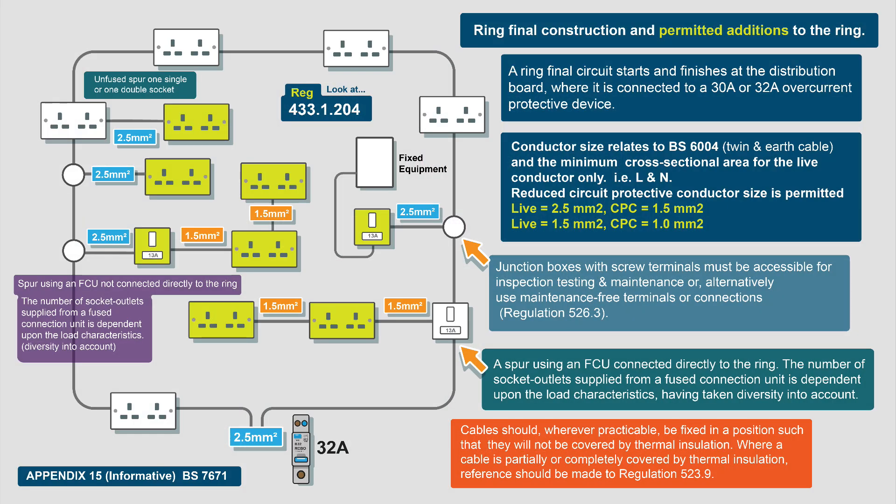In BS 7671 you'll find Appendix 15, and this tells you how a ring final circuit is constructed and any permitted additions. Basically, a ring final circuit starts and finishes at the distribution board and is connected to a 30 amp or 32 amp overcurrent protective device — it's generally a 32 amp RCBO nowadays, but you will find many installations with a 32 amp MCB or even a 3036 rewireable fuse; plenty of those still about.